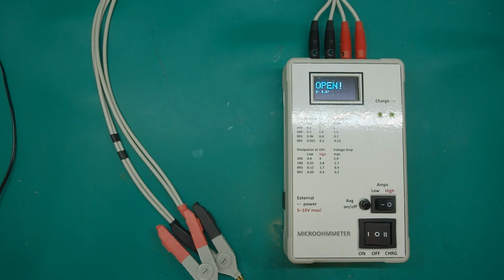Sometimes a micro-ohmmeter able to measure very low resistances, as low as 1 micro-ohm, is quite a useful tool. For example, when measuring contact resistance of relays, switches, fuses, and other mechanical connections and contacts. It can be used to test transformers, rotors of electric engines, and so on.